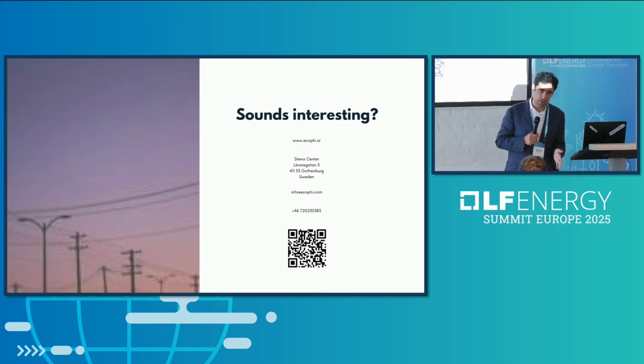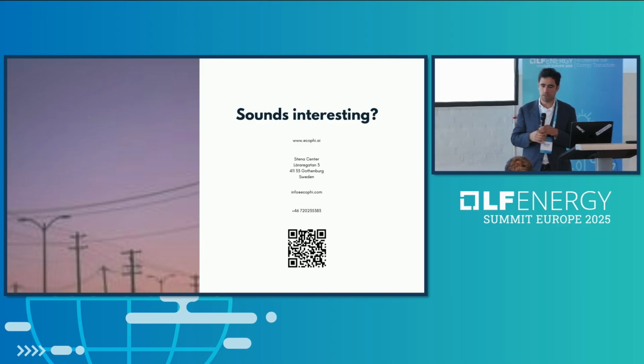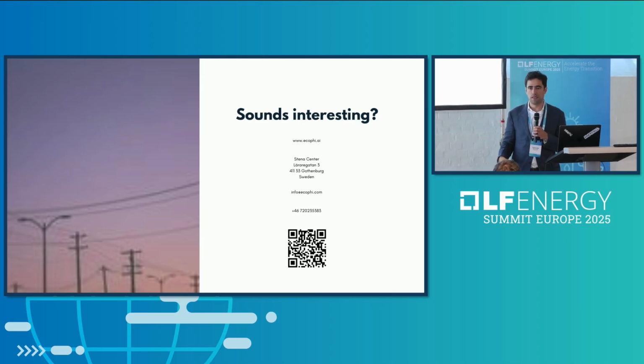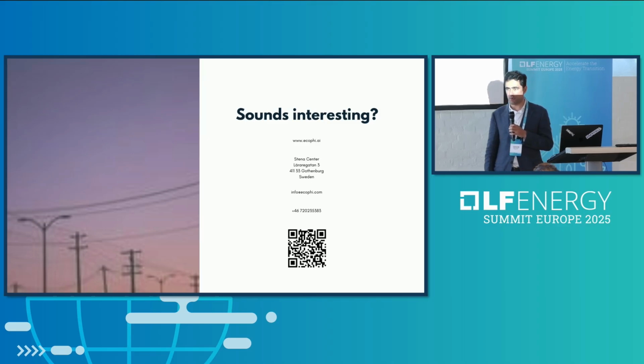We've had cases, for example, where thunder hit the line, damaged the transformer, and the tap changer wasn't working fine, and we highlighted that the transformer was going to fail. Or when we say insulation degradation is happening and there's going to be a potential failure because of that, we say the location is here. Because we have a 2 megahertz sample rate, early intermittent cases can be seen as they travel, and so on. Using these methods, we can locate them early on, and the location of faults becomes much more straightforward.